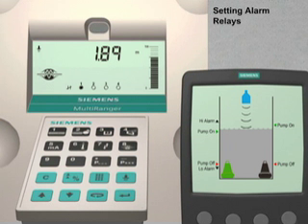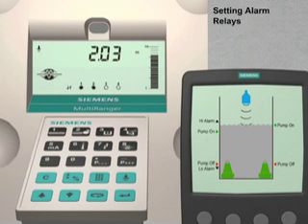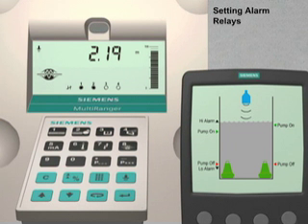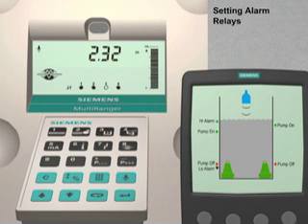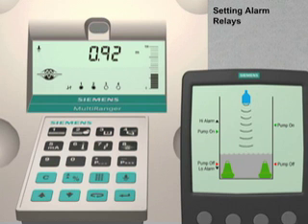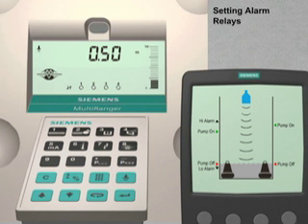Pump number 2 turns on to assist pump number 1. The filling rate slows again but the level continues to rise, as the liquid is coming into the vessel faster than the pumps can pump it out. The high level alarm comes on to warn the operator of a potential vessel overfill. Finally, the liquid inflow rate decreases below the pumping capacity of the two pumps and the liquid level begins to drop. The high level alarm turns off and the pumps continue to pump down the liquid until they reach their offset points. The Multiranger is now fully configured to control a basic duplex pumping station.